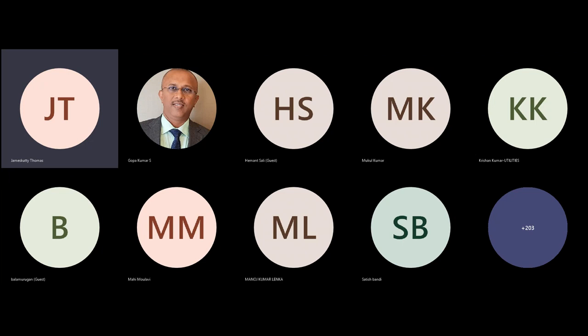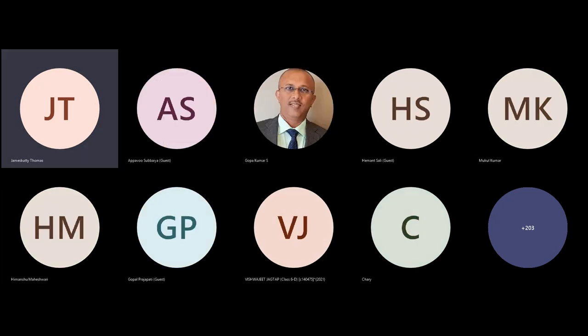I don't know from which point you heard it clearly. Anyway, the distribution boards are open and accessible to humans. Clearances are actually not followed properly. Guarding is missing. The earth conductor by the licensee is not implemented anywhere in India. So it is better, as we discussed, to clarify the related regulation with the type of system — TNC, TNS, TNCS, etc. Then we should insist on having at least earth fault protection, if leakage protection is not possible.